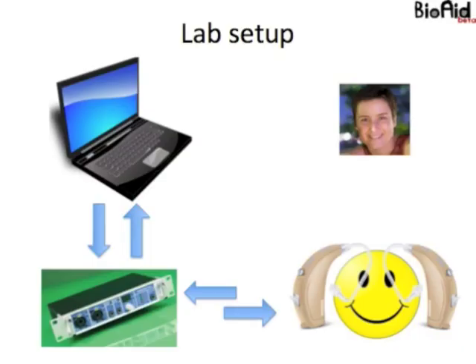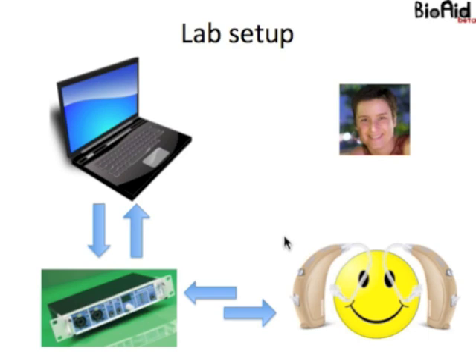Aside from the software I've just shown you, we have a fairly simple lab setup connected to this software. This involves the software running on a laptop connected to a high-quality sound card, which is in turn connected to actual hearing aids that a patient sits and wears. These are wired specially so we can connect them to the sound card. The only difference between having the hearing aid algorithm built into the aid itself and this outboard setup is just the bulk of it. My colleague Wendy LeCleuse has spent countless hours in the lab testing patients with all different kinds of hearing loss with the hearing aid.